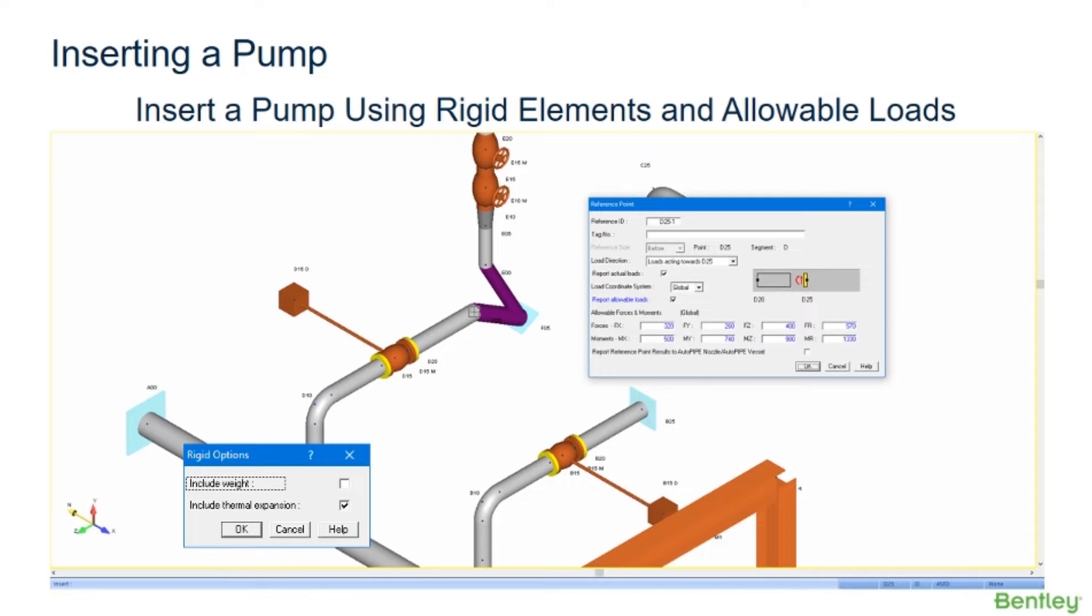Reference points can also be used to model the suction and discharge points of rotating equipment. With this method, a simplified modeling approach is to use rigid elements to model the rotating equipment, and this allows for the modeling of the equipment and its supports.